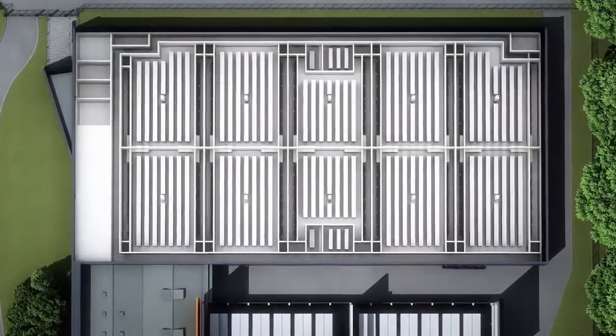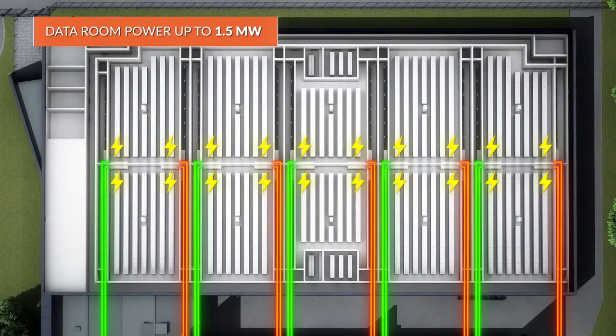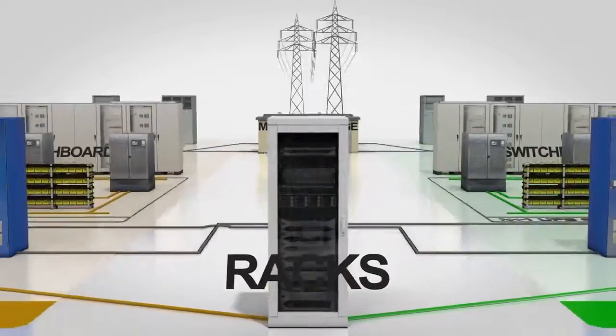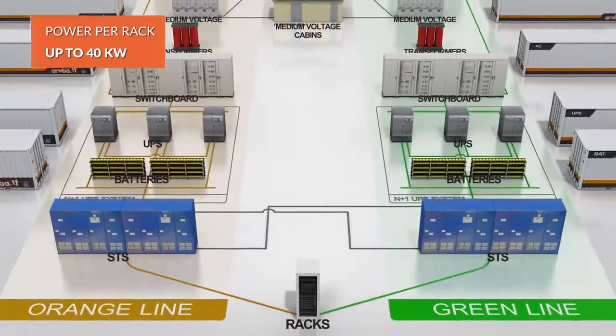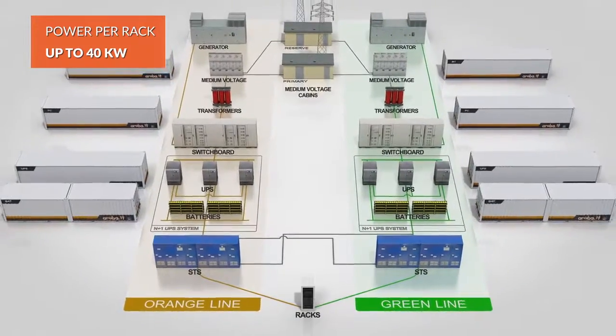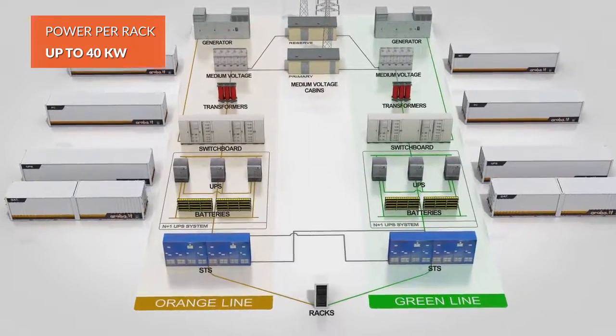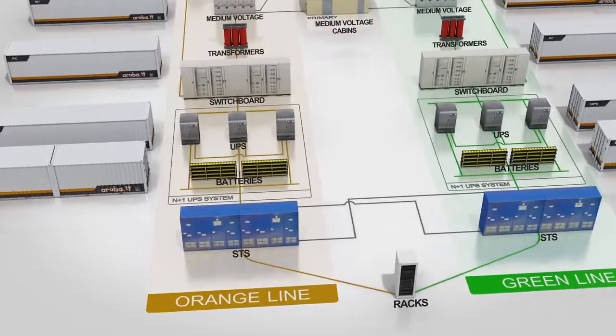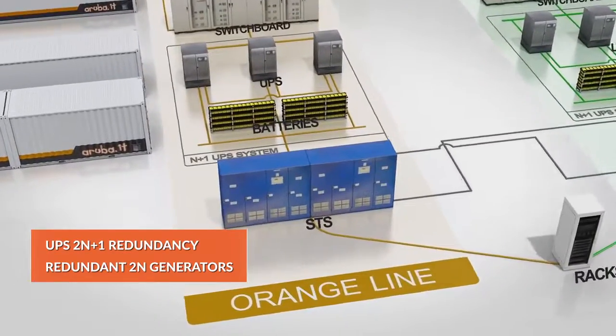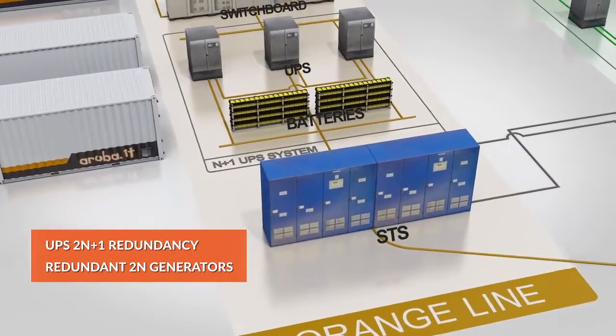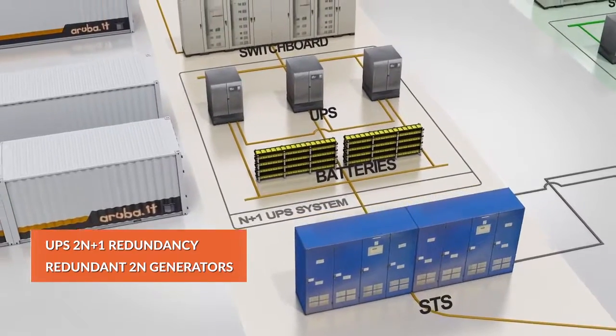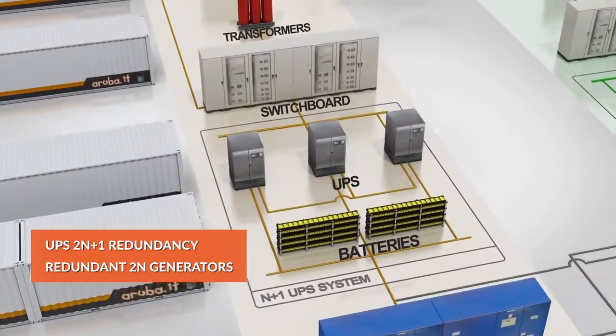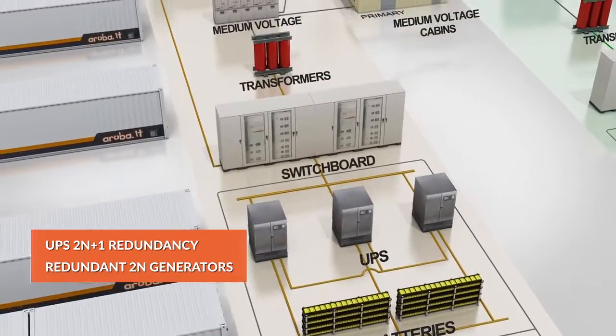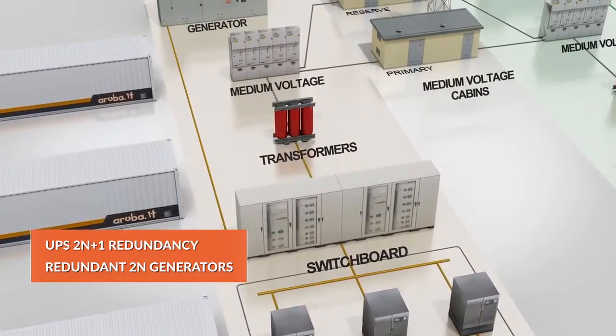The power for each room can be customized up to 1.5 megawatts. The racks have a power of up to 40 kilowatts. The power system's redundancy is total and includes both ordinary operation with 2N+1 UPS units and backup operation with generators, which are also redundant.